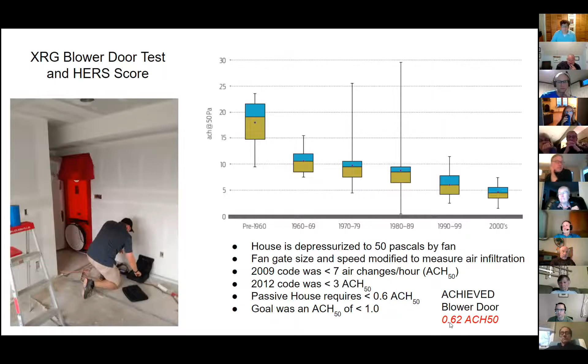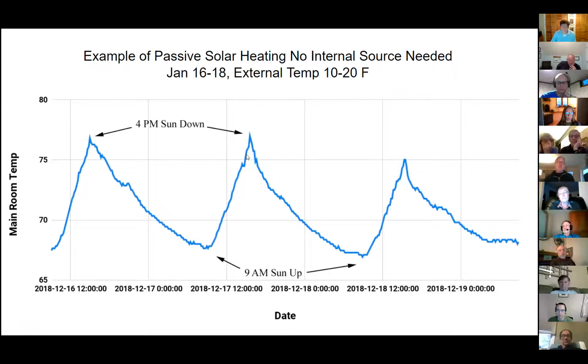So here's an example of our passive solar heating. Sometime in the middle of January, when the temperatures outside were 10 to 20 degrees, we were able to turn off our heat pump. And then you can see the temperature would go between 68 and 77 as the sun would come into the windows and heat the concrete floor. And then that would slowly dissipate till about 9 a.m. when the sun would come up again. So we could go back and forth, back and forth. And as long as the sun was out, we didn't have to have the heat pumps on.